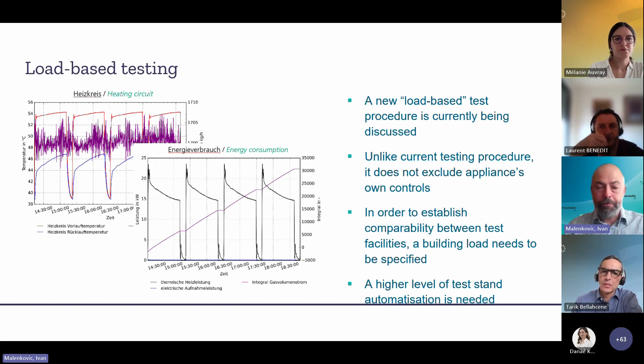So you impose a fixed heating or cooling load and let your heat pump run, which leads to quite unsteady behavior, especially in some part-load conditions. This requires extra skills, and you also need to use some inertia, some building loads, which is a model given to the test lab as a building model. It gives the inertia of the real house, but also the inertia to the hydraulic system of your test rig control. This means that in most cases a higher level of test automation is needed. This is not yet a current test method, but it might be the future of testing, something we may have to face soon.